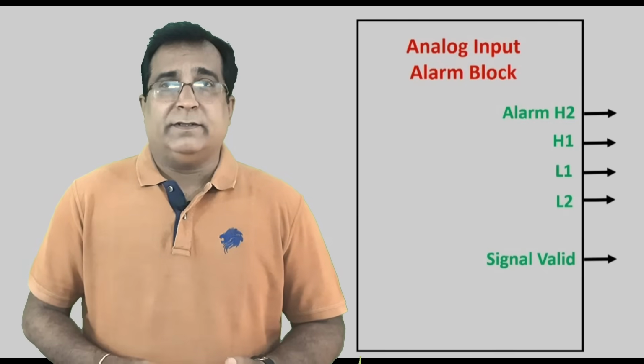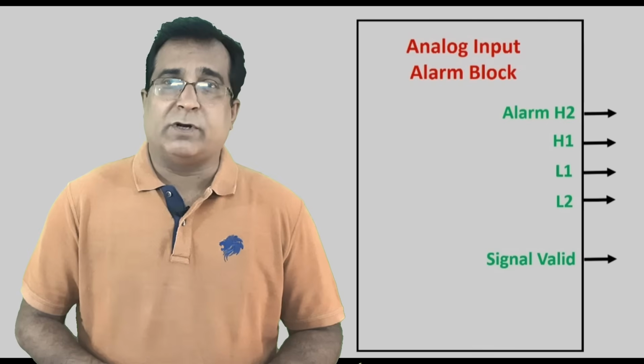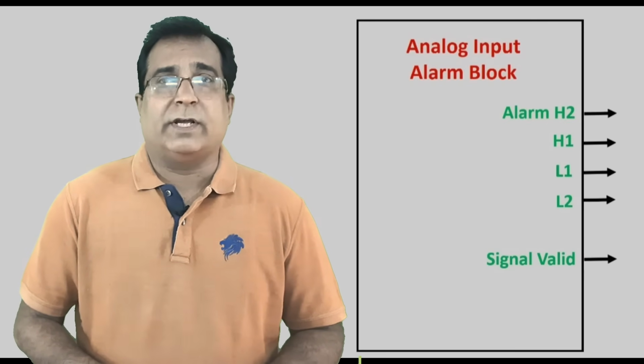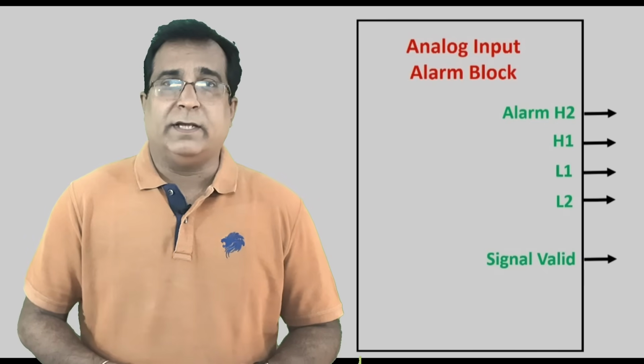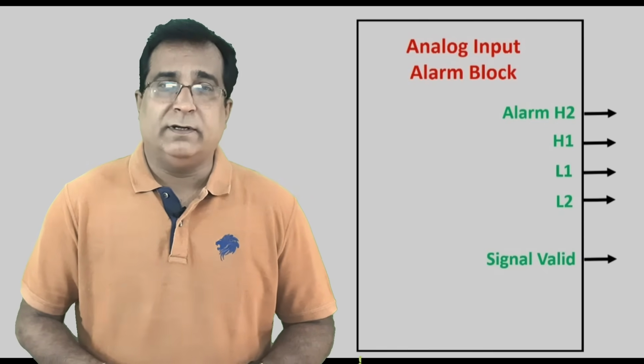But keep in mind that you need to interlock this bit before the analog input limits are programmed in the program scan cycle. Programming this live 0 bit after limits interlock execution will trip the equipment, as all the limits are set to logically 0 at the time live 0 is encountered.